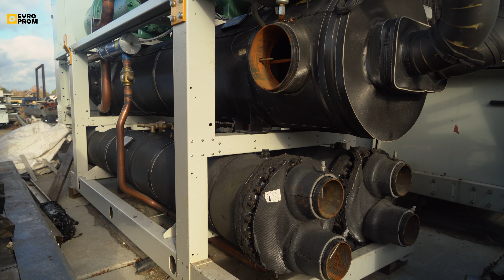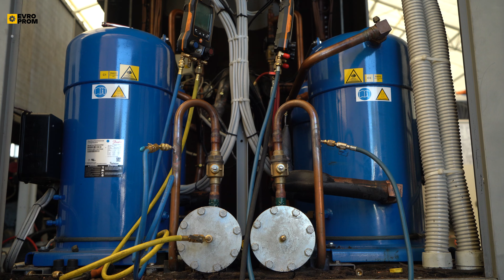A chiller can have 1 to 4 refrigeration circuits. The easiest way to guess how many circuits it has is to count the filter dryers. They're usually easy to spot. 1 circuit equals 1 filter. If you see 3 filters, chances are the chiller has 3 circuits. Most small chillers are single circuit, while medium and large units are 2 circuit. Of course, there are exceptions.